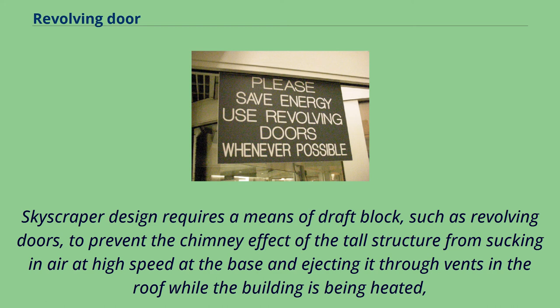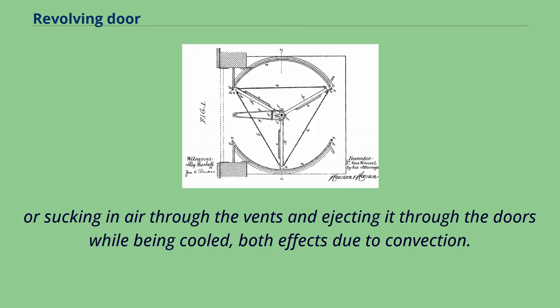Skyscraper design requires a means of draft block, such as revolving doors, to prevent the chimney effect of the tall structure from sucking in air at high speed at the base and ejecting it through vents in the roof while the building is being heated, or sucking in air through the vents and ejecting it through the doors while being cooled, both effects due to convection.